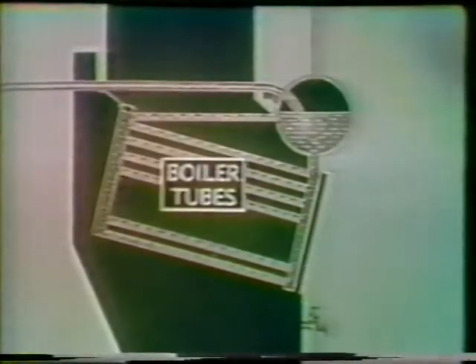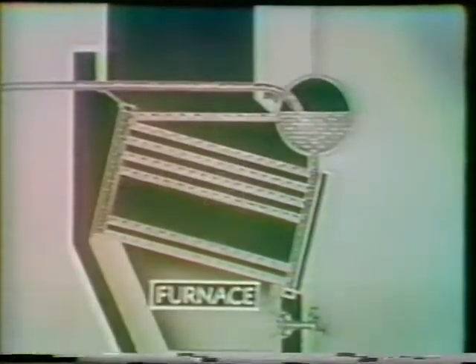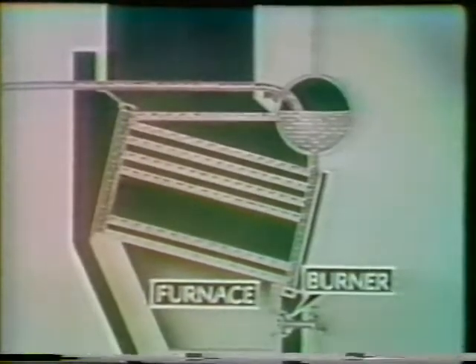Let's see how these phases have been developed in the efficient power plant of a modern vessel. In contrast to the primitive boiler, today's naval boiler is designed to get as much as possible of the heat energy out of the fuel and to produce steam of high pressure and temperature. Generation may be shown in this simplified boiler. The hot feed water enters a drum and fills several thousand feet of tubes. Underneath is the furnace with several burners.